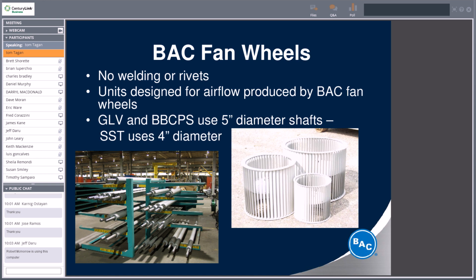This is just showing, this is for the centrifugal fan. On the left, you'll see the stainless steel shafts. On the stainless steel, we can get away with a smaller shaft. We also use galvanized, but again, that's an upgrade that'll prolong the life. With your shaft, sometimes it's hard to decide whether you've got a little surface corrosion or whether that shaft is ready to go. So a stainless steel shaft upgrade is not a bad idea. Centrifugal fan on the side, fan blower here, the squirrel cage.